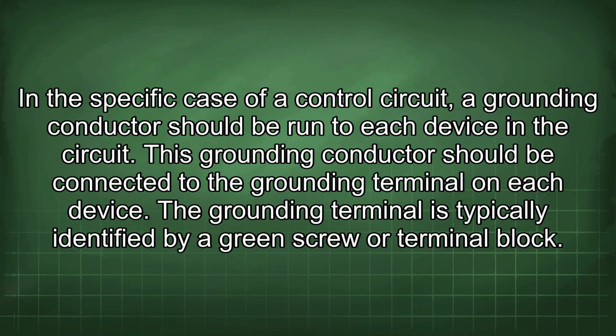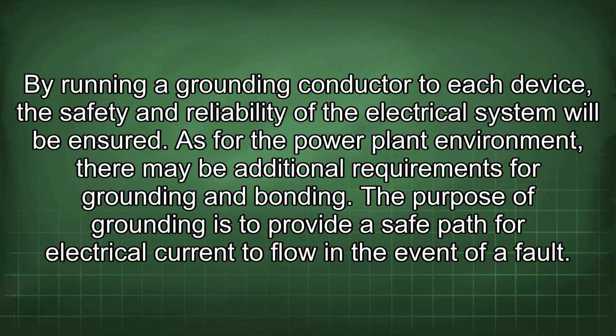In the specific case of a control circuit, a grounding conductor should be run to each device in the circuit. This grounding conductor should be connected to the grounding terminal on each device. The grounding terminal is typically identified by a green screw or terminal block. By running a grounding conductor to each device, the safety and reliability of the electrical system will be ensured. As for the power plant environment, there may be additional requirements for grounding and bonding.